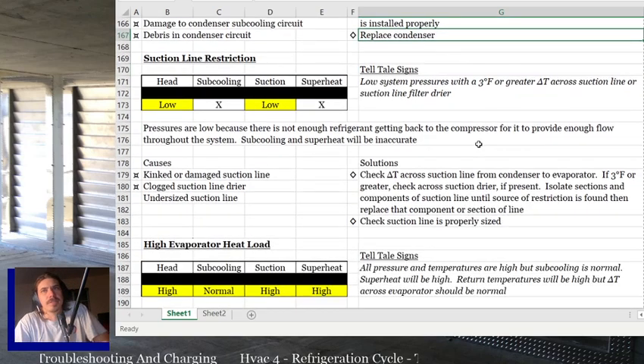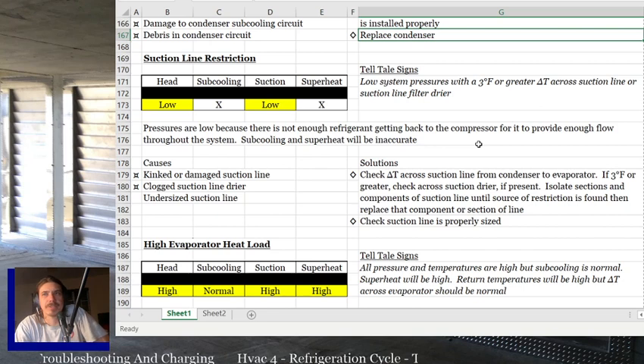Suction line restriction. Suction line restriction is tough. It usually just looks like low charge. It's one I want to play with and see if I can get some results that'll help us figure it out. A lot of times the suction line restriction's a head scratcher if it's not obvious, and it's obvious when you have a suction line dryer. If you don't have a suction line dryer, it's a weird one if you can't see the restriction.